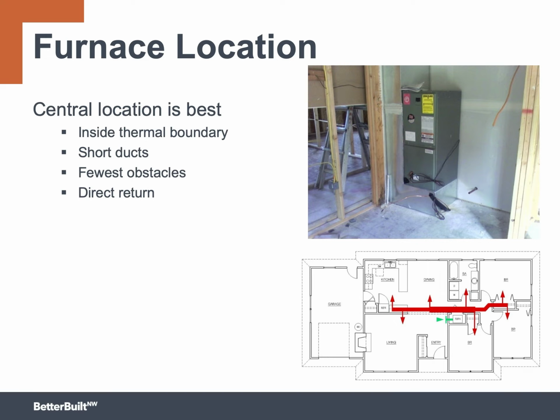Now let's talk about where to put the furnace. A central location is always best. It's inside the thermal boundary, the duct runs are going to be much shorter, you'll encounter fewer obstacles, and it's possible to have a really short return or no return at all. If you want to eliminate the return duct, use what's called a direct return, where the air goes directly into the furnace through a louvered grill. There's no duct at all. It's not the choice that many builders make, but I just want to mention it as an option.